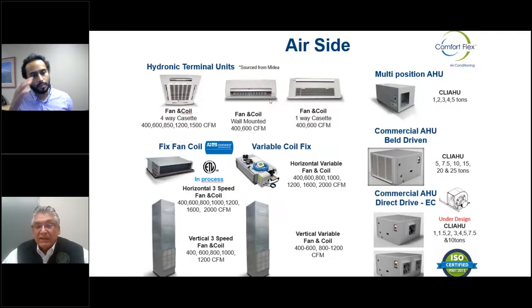As a total package, we use Carel as our controllers. We can actually put a complete system together that'll give you variable speed everything. Those have been around for a while. The Hartman loop was a big push some 20 years ago. About everything was variable speed.